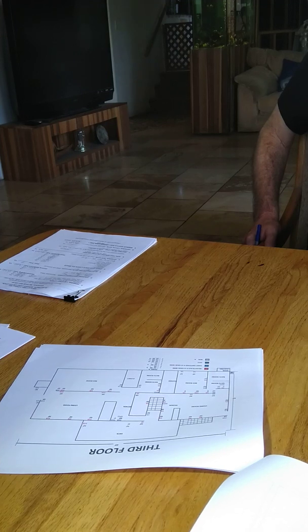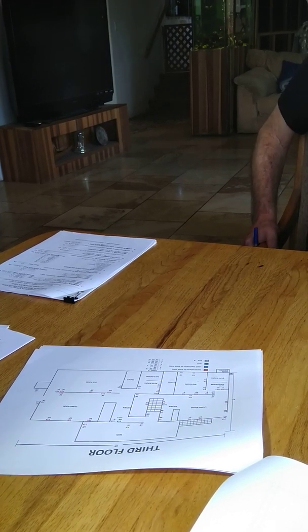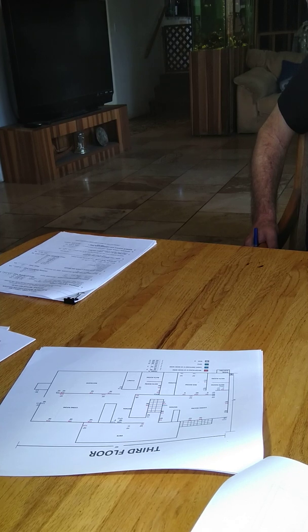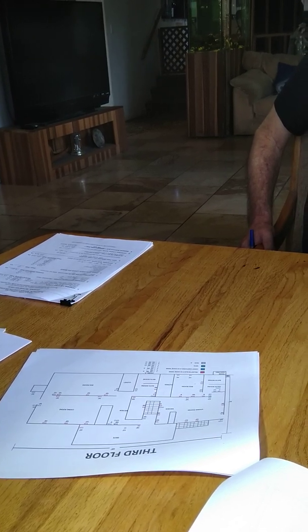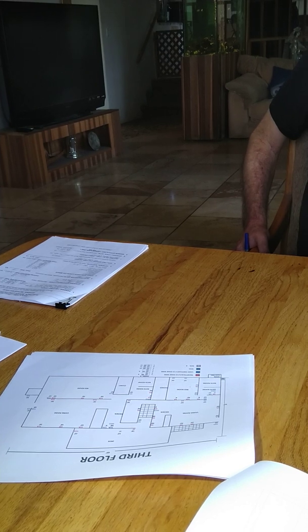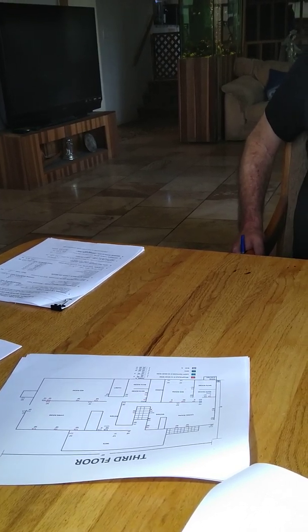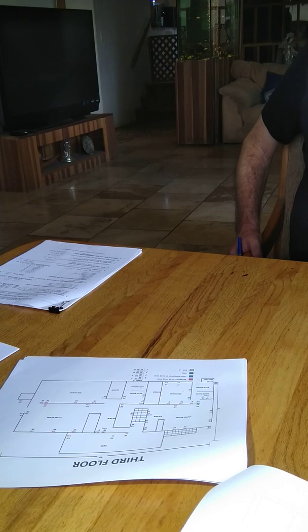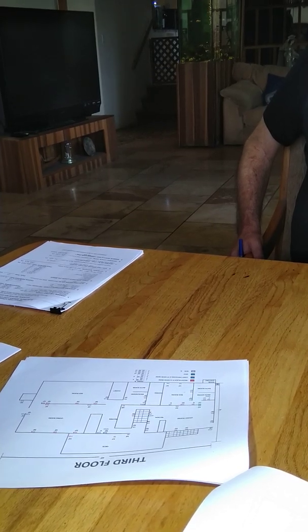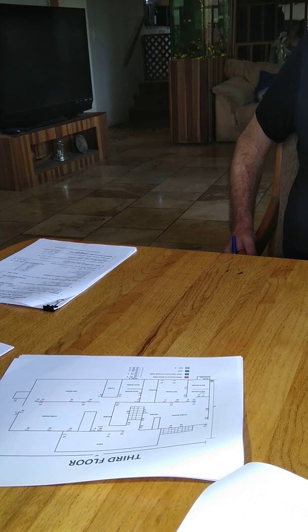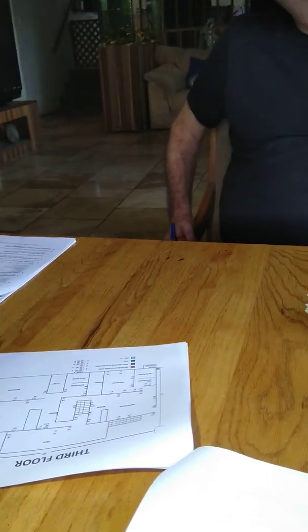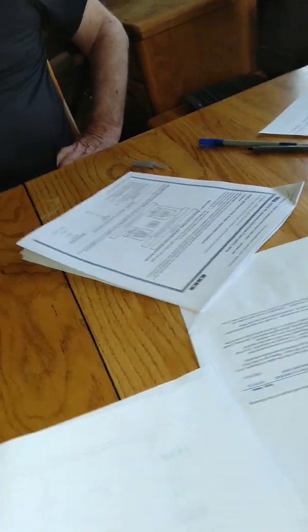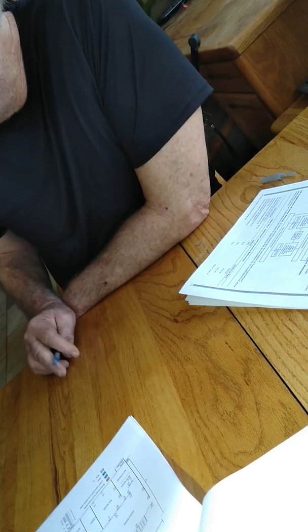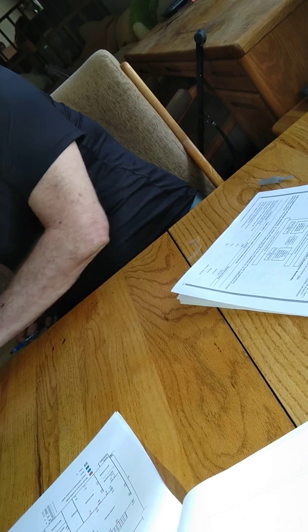But it's a 120 volt pump. That doesn't matter. We're just talking about amperage right now. Yeah, but if you double the voltage, doesn't that reduce the amperage flow because you're at 240 instead of 120? I'm going to base it off of the actual amperage itself. So if you're looking at a 40 amp circuit breaker out there and you have a number 8, and number 8 is rated for 40 amps, now the concern would be the length, and you have to derate the conductor because of the length that it's being run out there, which is 250 feet. Okay. So there is a concern.